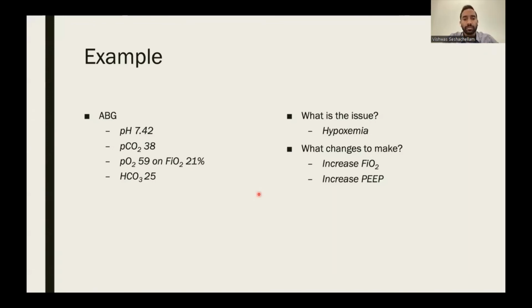No, we can change the flow rates from 5 to 8. So the flow rate shouldn't make a difference though. If you change to 100% FiO2, as long as you have fresh gas flow at a certain rate, I think the machine will automatically increase the flow rate. Right, because if you change this FiO2 from 21%, that's just room air. If you change it to 30%, that'll be an admixture of room air and oxygen. And if you go to 100%, it'll solely take from the oxygen source and provide that flow so that you achieve this FiO2 of 100%.